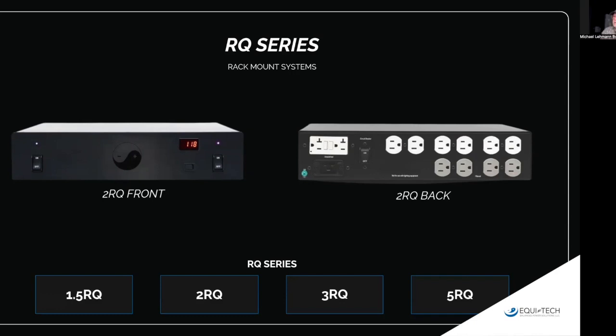So for those of us who don't want to rewire, taking individual units off of the feeds from the 200 amp panel would be the way to go - except if it's coming from the transformer and gets to the main 600 amp split, where it splits out 600 amps to the 200 amp sub panel, that's still 220 at that point. It splits into A and B legs at 120 each, so you have 120 volts on either L1 and L2. It's not like rewiring from that point - it's rewiring from the main 600 amp insert to the 200 amp breakout boxes.